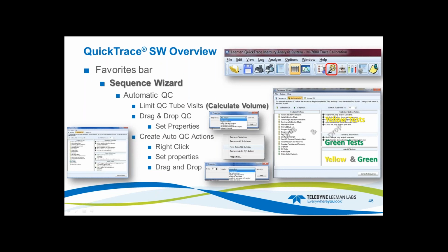And also, this is an interactive, so again, we're in the Sequence Wizard Automated QC, so it's drag and drop. So yellow's up here, that's your quality control for your standards. Your quality control for your samples is down here, green, and on the bottom you can create your own. So right-click, set properties, and drag and drop your quality control down into here.